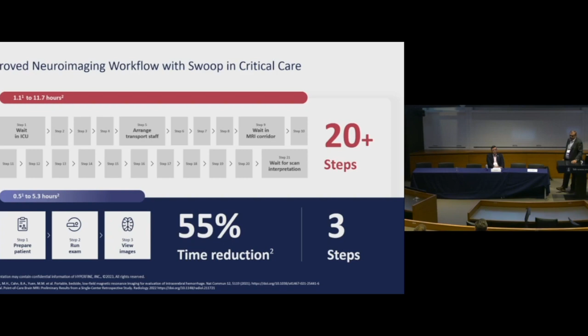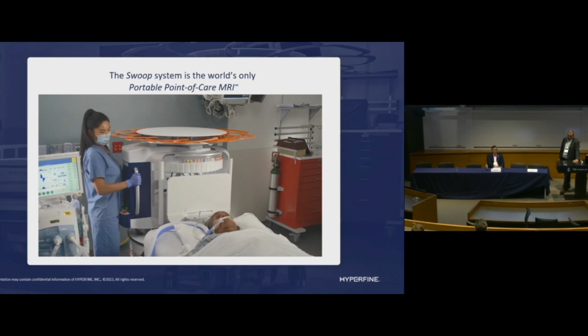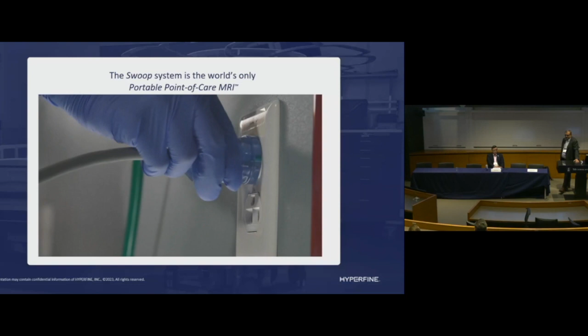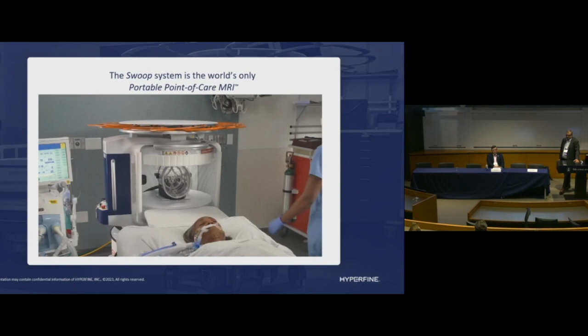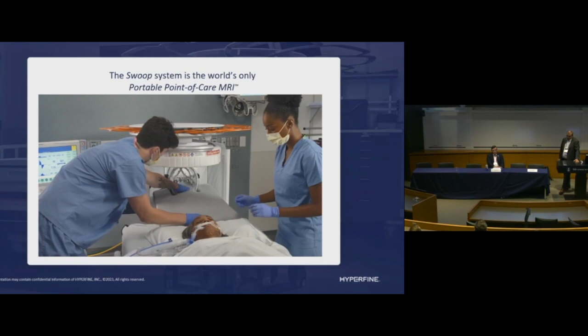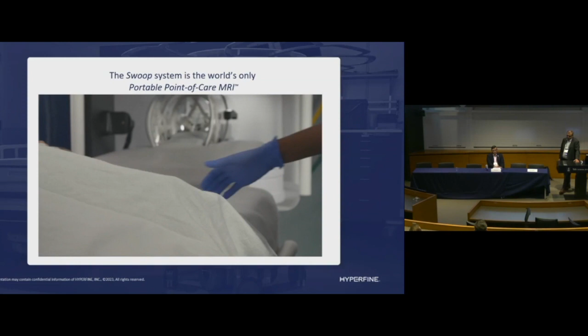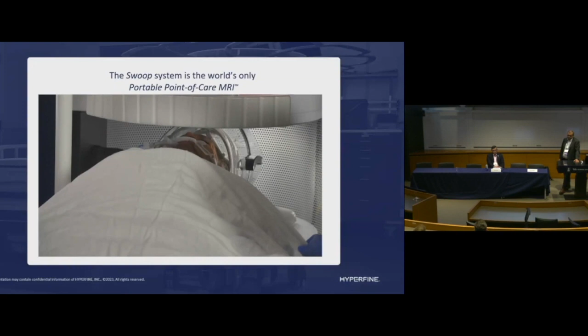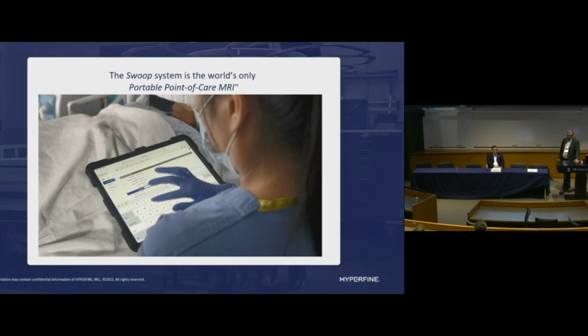Swoop is a portable MRI system that allows clinicians to take pictures of a patient's brain without the patient leaving their room. The system enables physicians to access those images within minutes instead of hours. Hyperfine designed the Swoop system to ensure low risk to the operator, patient, and nearby medical staff or family members. Swoop does not use ionizing radiation to generate images, unlike portable CT and X-ray devices. To begin imaging, ICU nurses will gently slide the patient into the transparent head coil. During the scan, the patient will hear low-level rhythmic tones and should remain as still as possible.